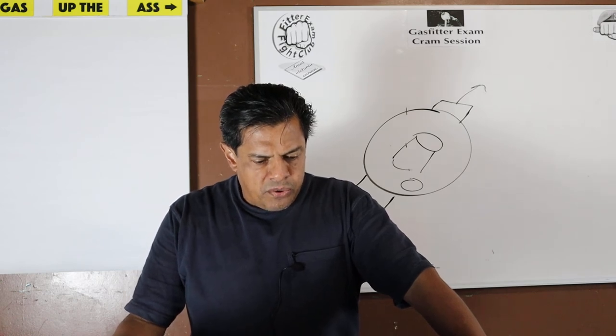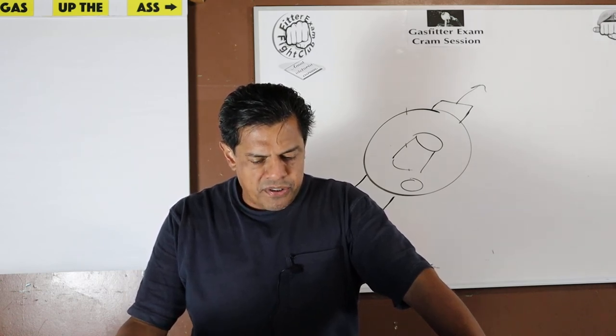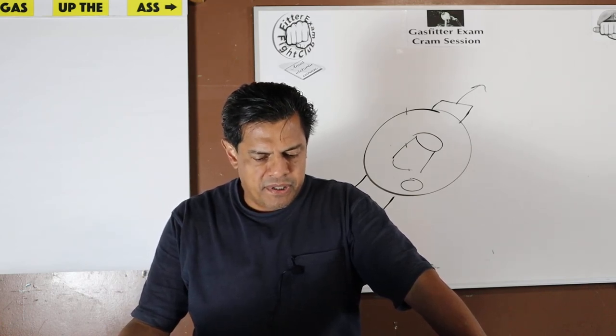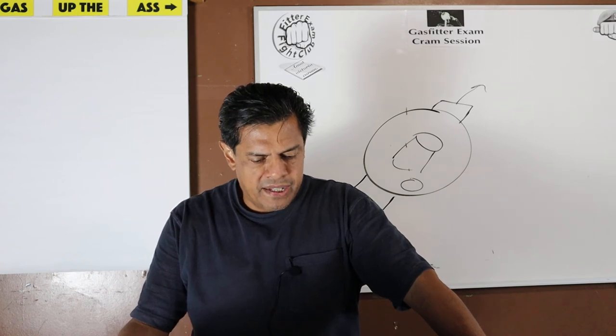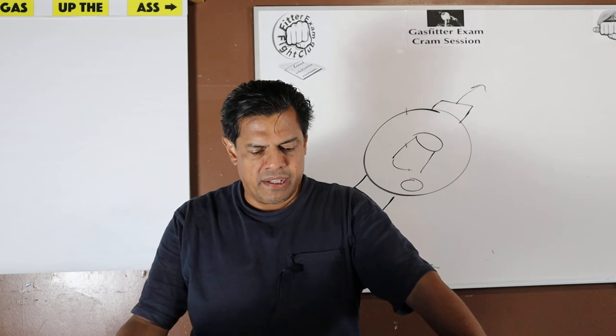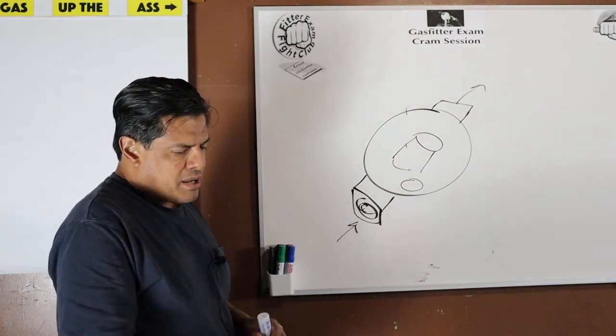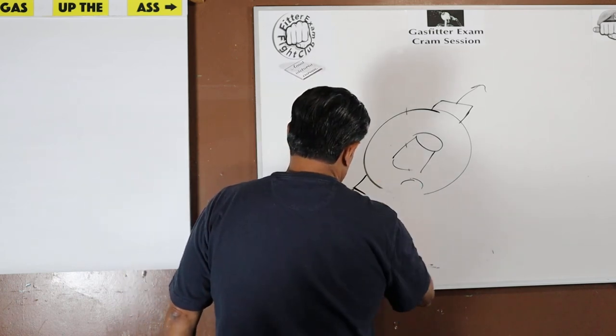19, to allow connection of a pressure measuring instrument, a T-fitting with one capped opening shall be installed not more than 10 pipe diameters downstream of an MP regulator. This is where it was good. We went over what MP means. So let's describe what they're talking about.